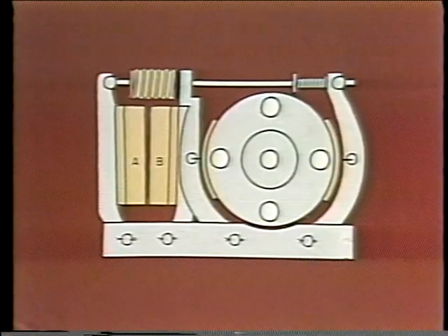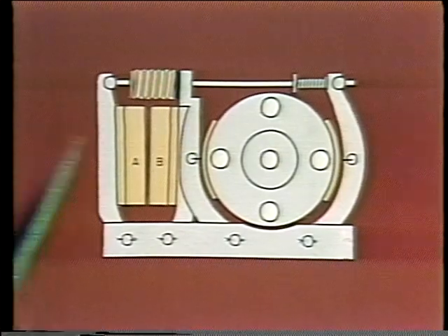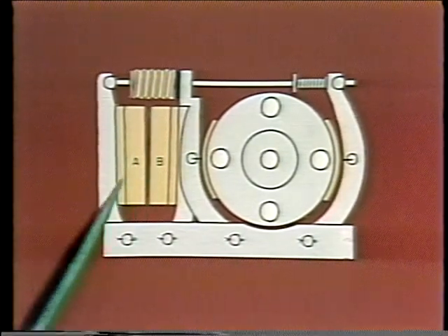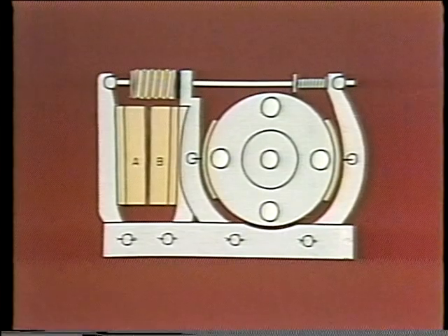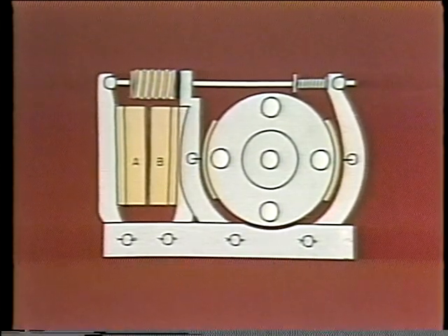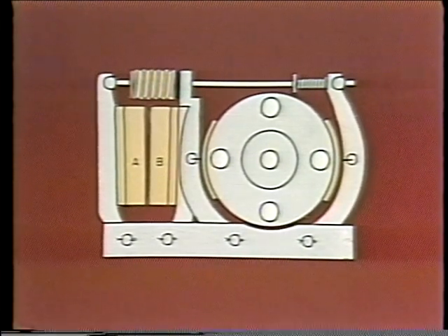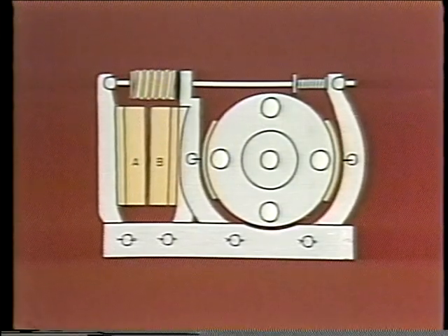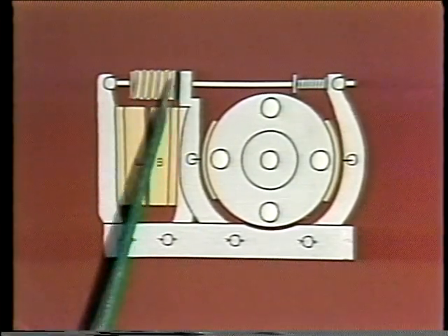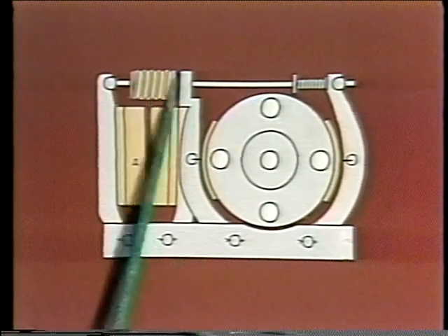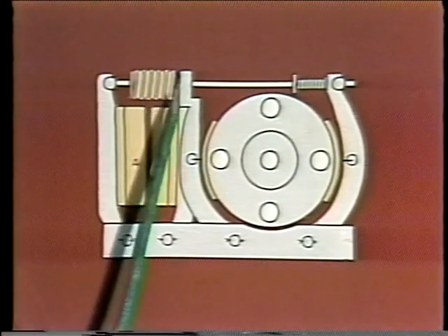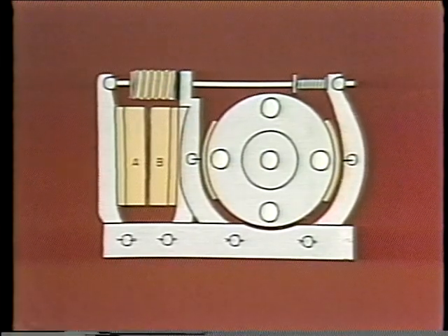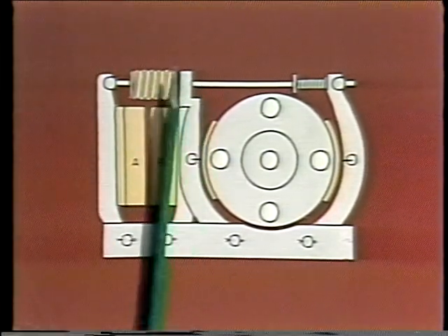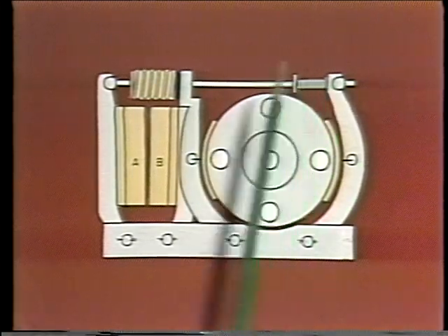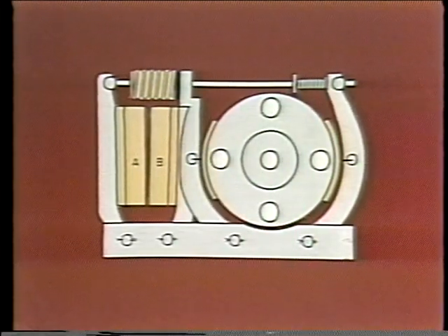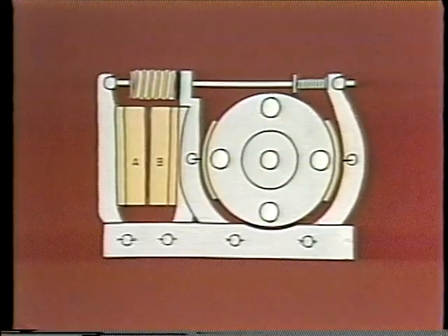Now, here's how the block brake looks when an electric coil, right here, is used to operate it. This type of brake is frequently used for heavy-duty applications, such as overhead cranes. In this case, as you can see, the coil pulls the plate over, which compresses the spring and releases the brake. When the current goes off, the spring actuates the brake. This unit is also sometimes called an external drum brake for obvious reasons.